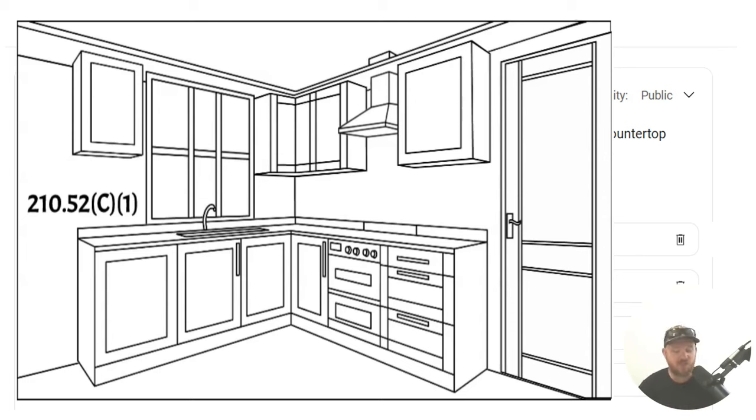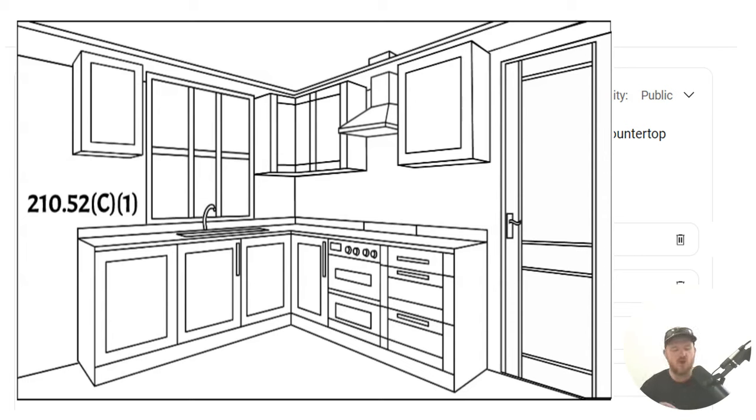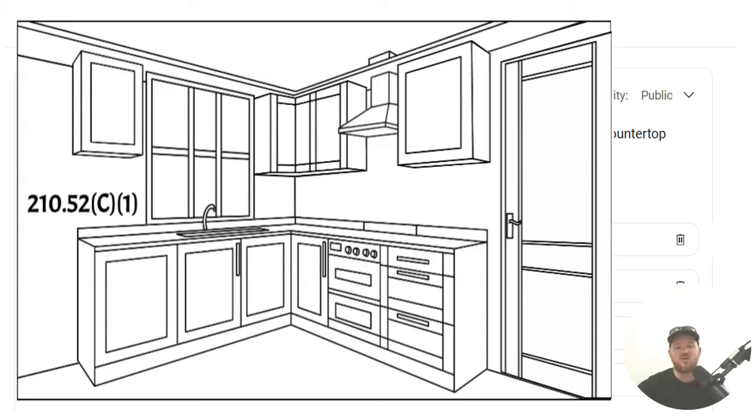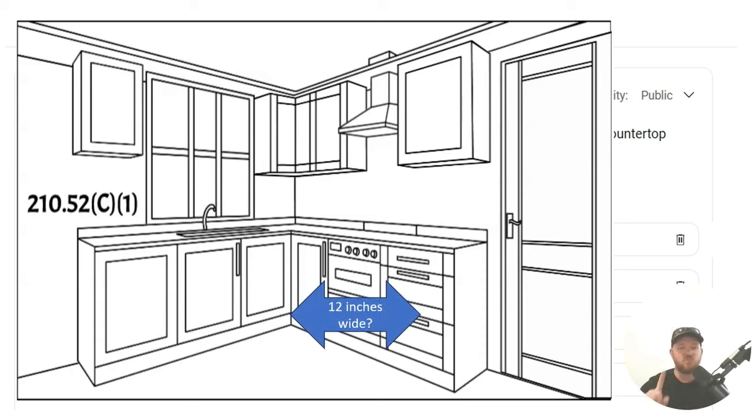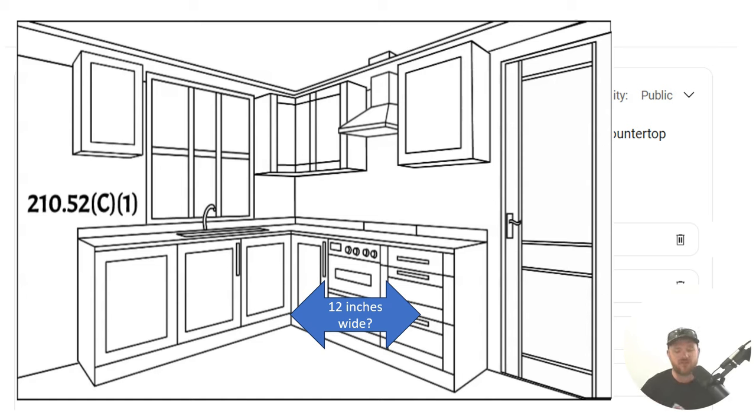When we get there, we find out that receptacle outlets shall be installed on work surfaces or countertops that are 12 inches or wider. So the first question we're going to ask ourself, is this countertop 12 inches wide? If it is or wider, we know that we're going to have at least one receptacle outlet servicing that countertop. Now let's read on.